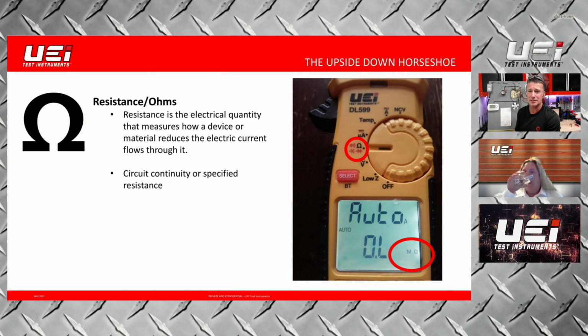So what are we doing with resistance? We're applying a very small DC voltage—I actually did it a while ago with my DL40 to measure the voltage coming out, about 0.2 volt DC range coming out of our meter. We apply a very small DC voltage onto our component and measure how much resistance of flow we have through that component coming back to the meter. It's important to understand that on the ohms setting, we don't want to check voltage, and we don't want to apply power onto an instrument that's already generating a small amount of power. There's no live voltage on it, which is why I just killed voltage going onto our supply source for our actual test board.